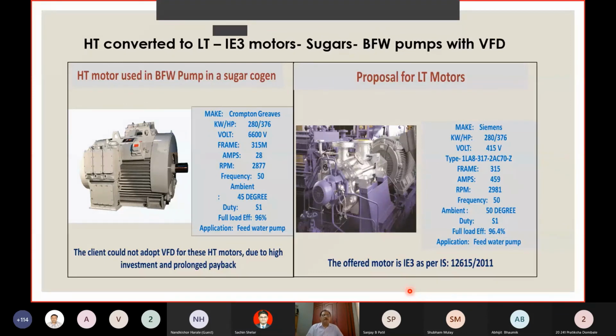Yes, sir. Okay. I've just shown one case study here where in a sugar plant, because you come from an area where a lot of sugar plants are there, people use medium voltage motors for boiler feed pumps. Actually today, LT motors can be given up to 1750 kilowatt 690 volts. Almost 1100 kilowatt 415 volts. The technology has caught up with the HT area.